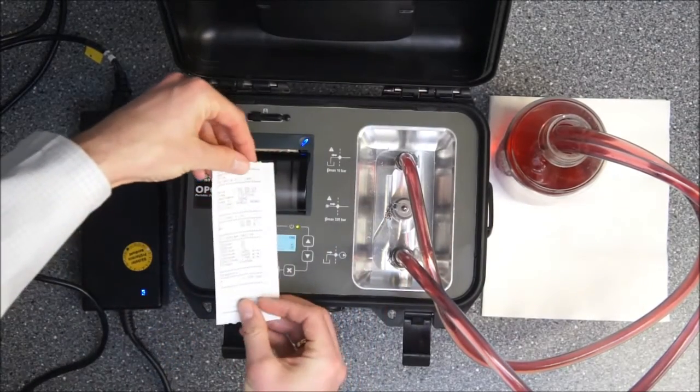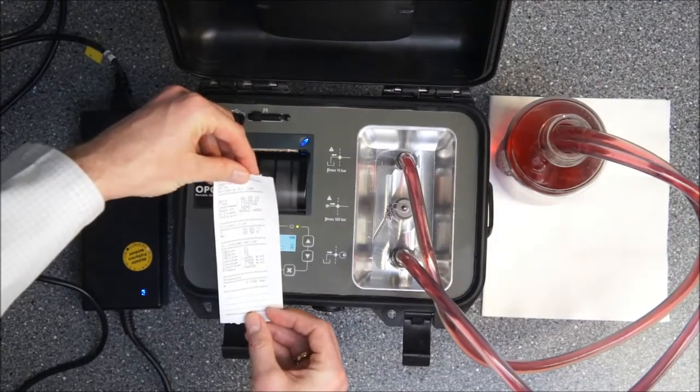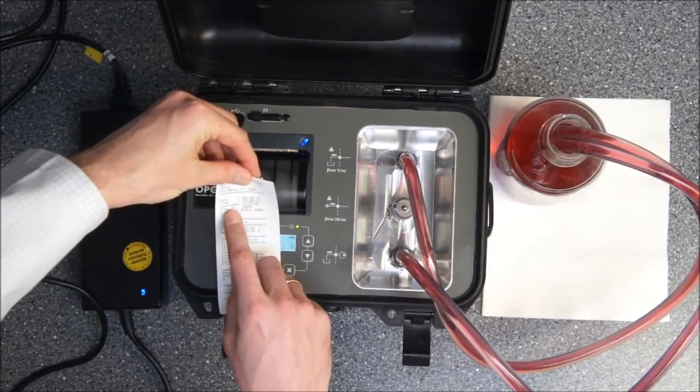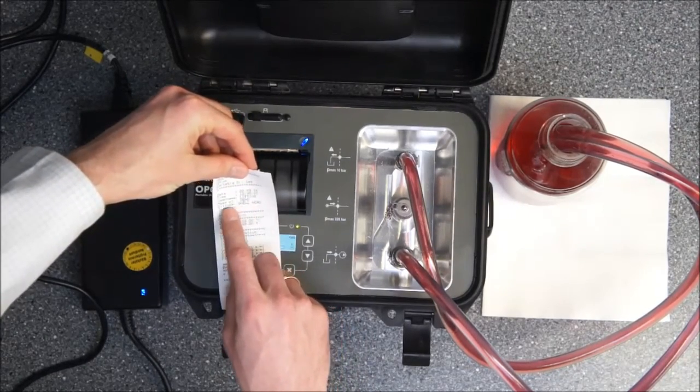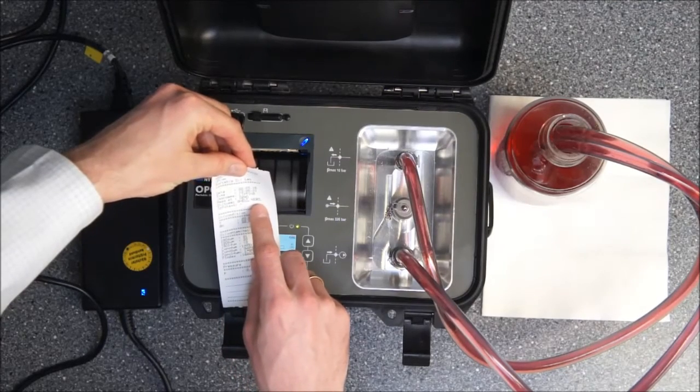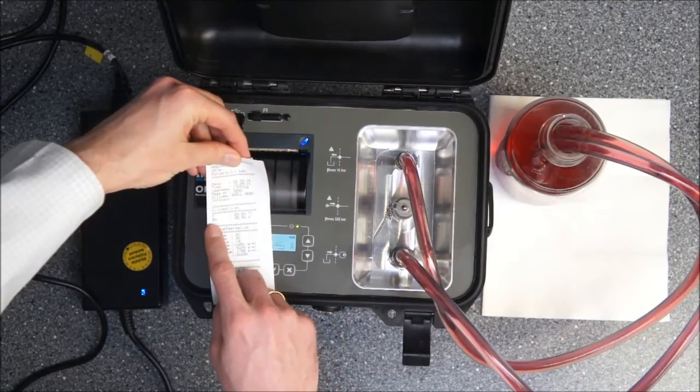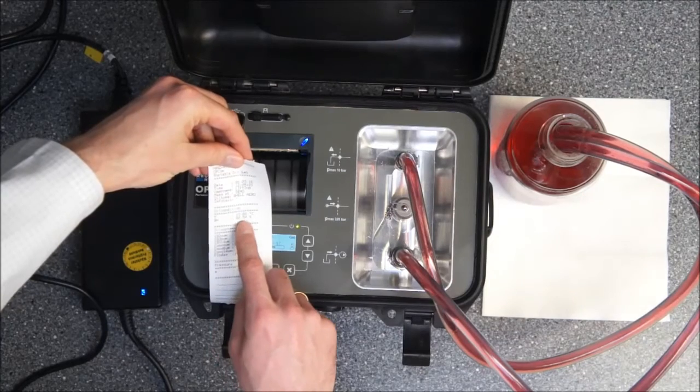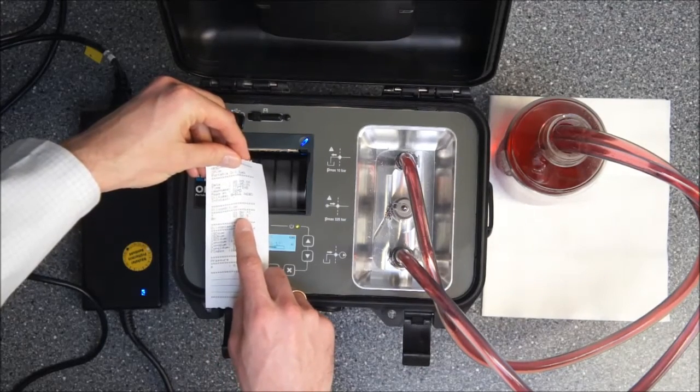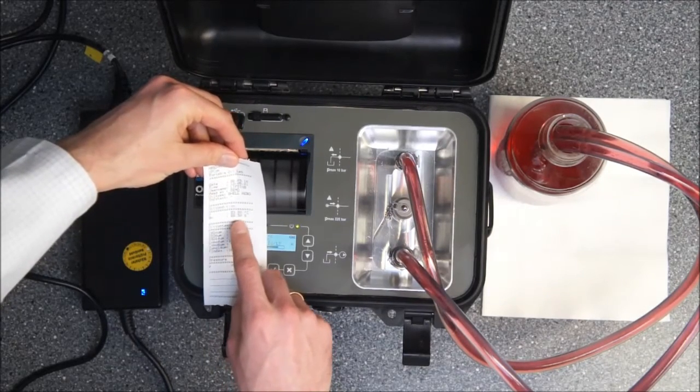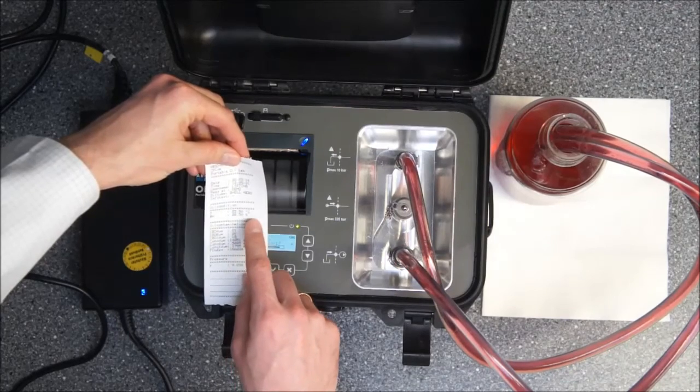On the printout you see now additional to time the place where we have done that, the measurement point. That's our demo and also the oil type that we have measured. Additionally you see the oil condition according to temperature and relative humidity. So we see temperature is approximately at room temperature and relative humidity is very low so our oil is in good condition.